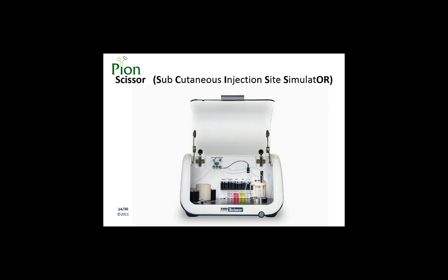The lid of the chamber is removed between experiments to replace the buffer sink and the injection cartridge. The stand to the right, situated above the drip tray, gives the user space to place the lid while they do this. Along the back, there are a series of wash, storage and calibration solutions for the electrodes.